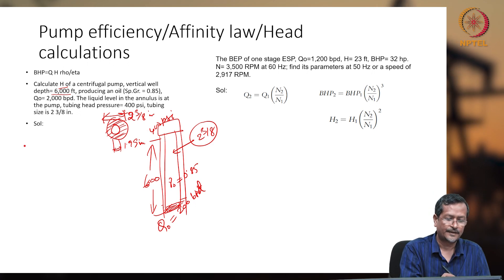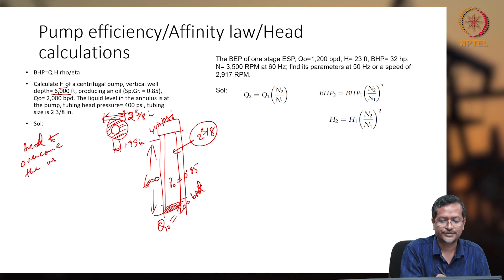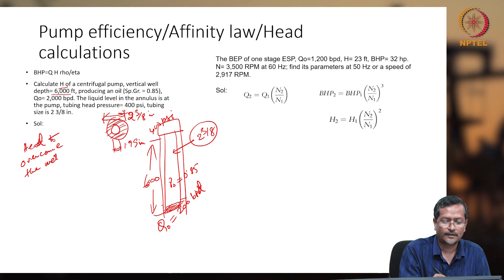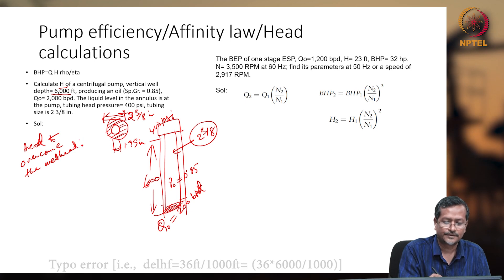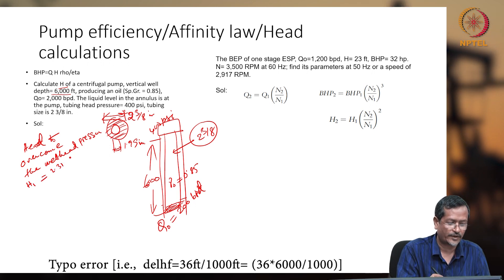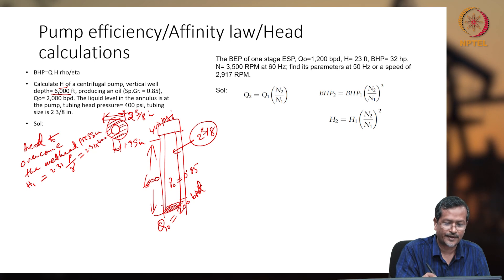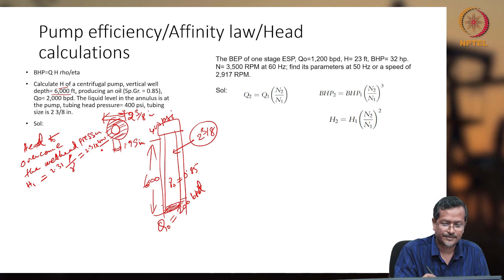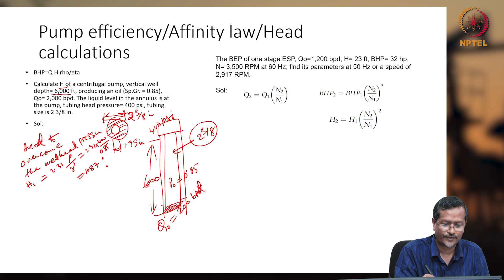Head to overcome the wellhead pressure: H1 equals 2.31 × P / gamma. Using wellhead pressure 400 and specific gravity 0.85, that gives H1 = 2.31 × 400 / 0.85 = 1087 feet.